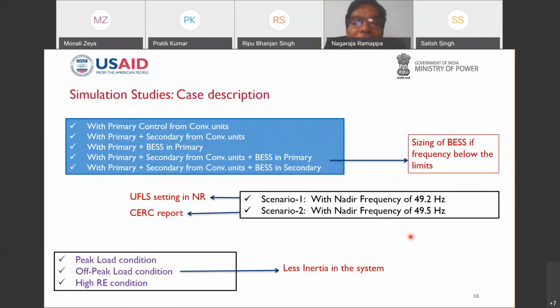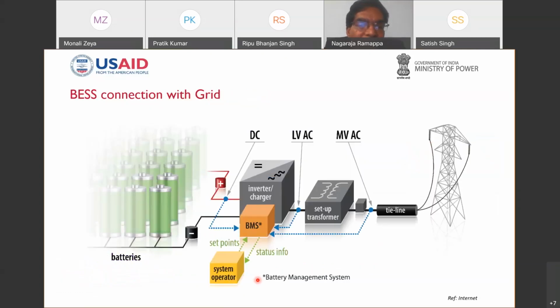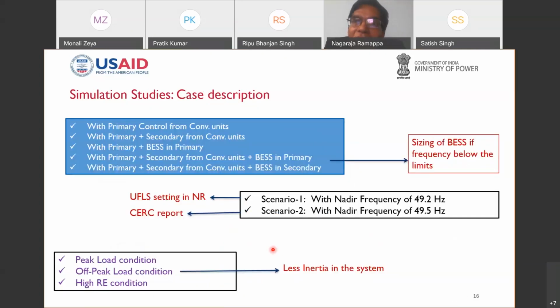Therefore, what is important in the various simulations is, in the case of the simulation studies in the southern region, sizing of the BESS, if the frequency goes below the limits, has been considered. Therefore, with the primary control from the conventional units, what happens? With the primary plus the secondary control from the conventional units and the battery energy storage system, what happens? These are the various scenarios being considered. And when it comes to the under frequency load shedding, even the nadir frequency is considered. And in order to have a sensitivity analysis, even 49.5 Hz is considered.